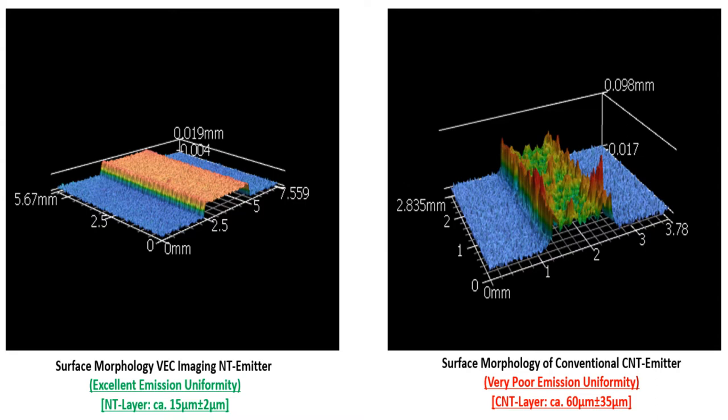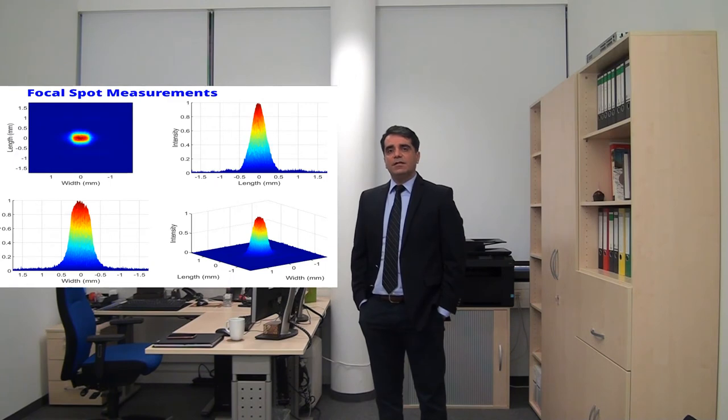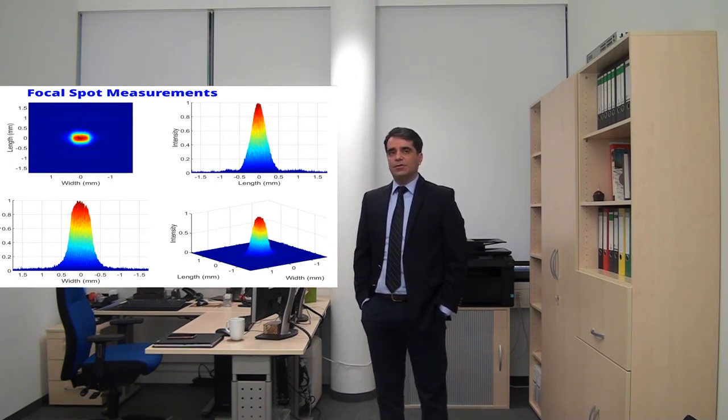And emitter lifetime. VEC Imaging's innovative material and production processes allow us to integrate hundreds of high-quality nanotube emitters inside a single X-ray tube enclosure. We have developed one of the most sophisticated and scalable electronic control systems, including an ultra-high-frequency high-voltage generator, to operate our X-ray tubes. It is a platform that can be adapted based on X-ray tube specifications.